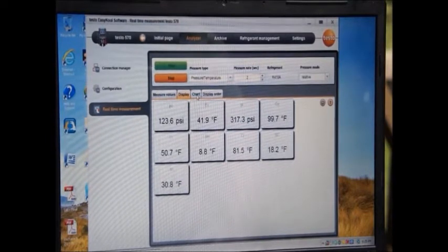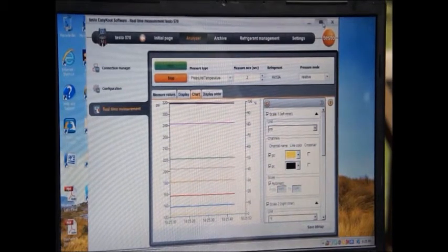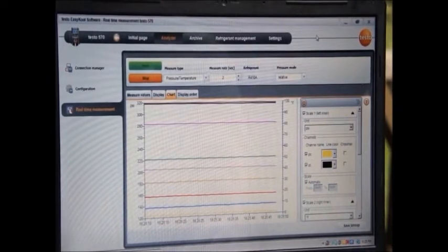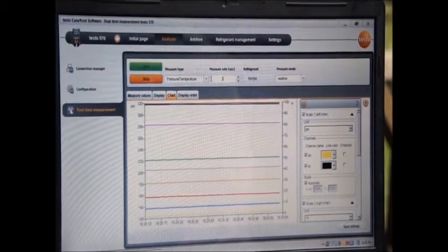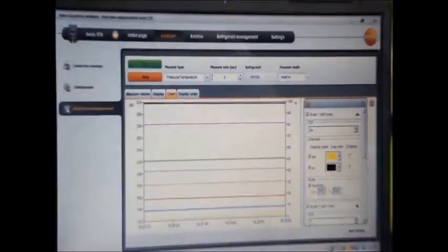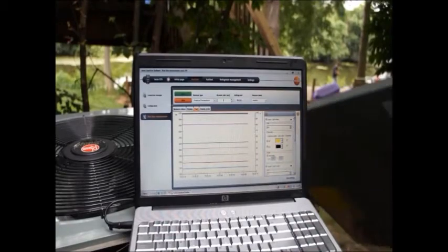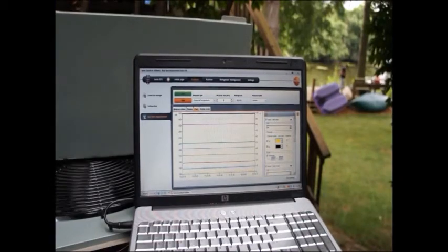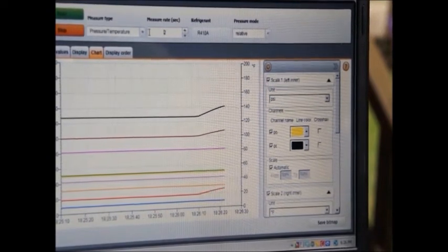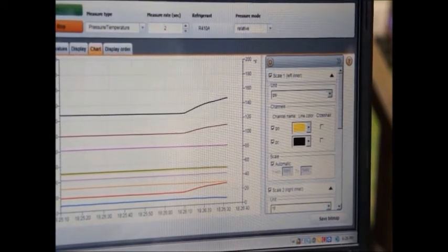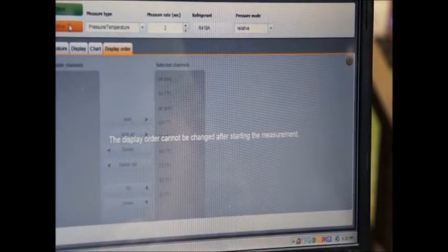If I go to my chart, it starts graphing these things graphically. I'm as wide open as I can get on my screen. Now I've got some pretty consistent readings there, everything is pretty smooth. I'm going to just block the condenser off for a second so we can see what happens. I'm going to put a panel on top of the condenser. What we're starting to see now is the high side pressure is going up and we're seeing really no change on our low side at all.